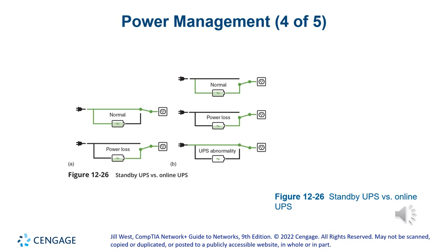Those batteries need to get replaced. Normally on the smaller UPSs, the lifetime is 4 years. It depends also on how many times they go on battery and the temperature of the room. The hotter the temperature, the less lifetime the batteries will have. Under normal conditions, like I said, 3 to 4 years is normal, but you have to set up a schedule to replace those batteries. On a larger online UPS, you also have to keep testing the UPS to make sure that the UPS is in good condition and that the batteries are at optimum.